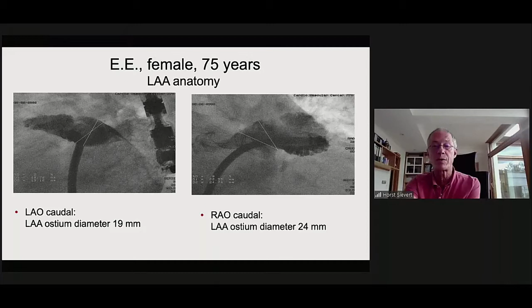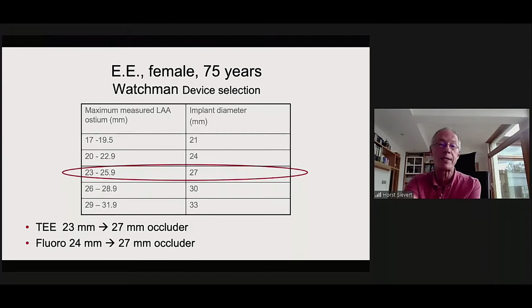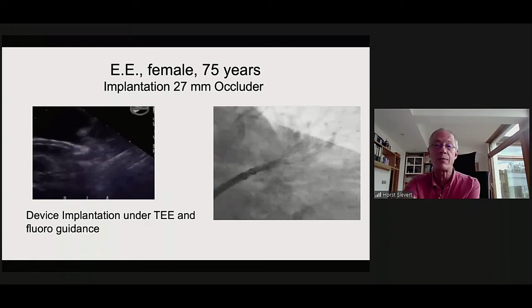So looking at the sizing chart, this was a patient where we closed the appendage with a Watchman device. We measured 23 on TEE, so that would end up in the 27 millimeter occluder, and also on fluoro, the largest diameter was 24. So a 27 millimeter Watchman occluder was the right size to go. This shows you the implantation of the device, some images from TEE as well as from fluoro. And this is the tug test. So we pull on the device to make sure that it's really engaged in the appendage.